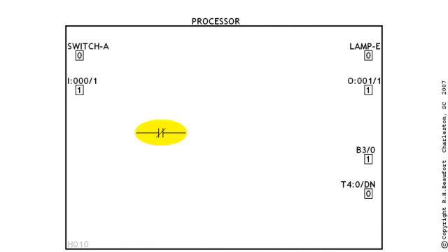Here's an XIO instruction and some bit boxes in the processor. Each time the processor comes to an XIO instruction in the program, the rule says that he's got to go look for a zero. The address tells him that he's going to look in the bit box named switch A. So the processor goes and looks in the bit box named switch A. Does he see a zero? And the answer is yes. So the processor goes back to the XIO and marks it as a true condition. And now he's done with the XIO for this pass through the program. That was simple. Here's another.